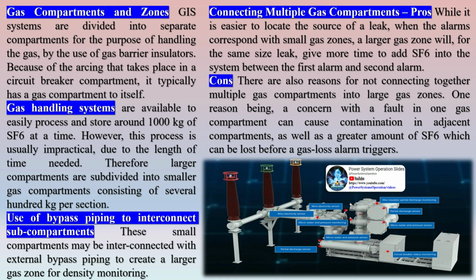Gas compartments and zones. GIS systems are divided into separate compartments for the purpose of handling the gas, by the use of gas barrier insulators. Because of the arcing that takes place in a circuit breaker compartment, it typically has a gas compartment to itself. Gas handling systems are available to easily process and store around 1,000 kilograms of SF6 at a time. However, this process is usually impractical, due to the length of time needed. Therefore, larger compartments are subdivided into smaller gas compartments consisting of several hundred kg per section.